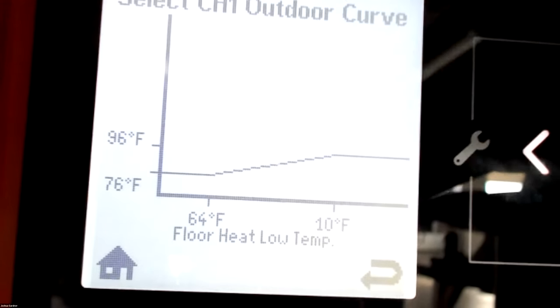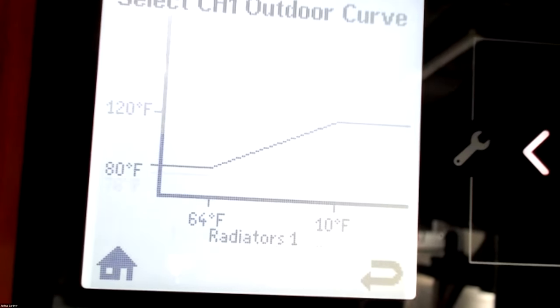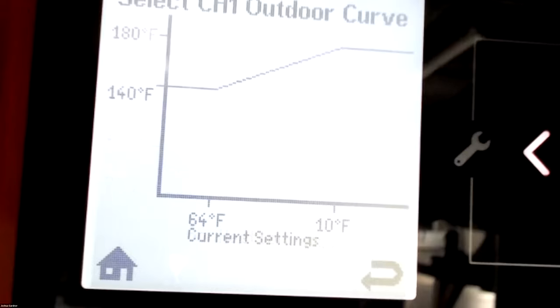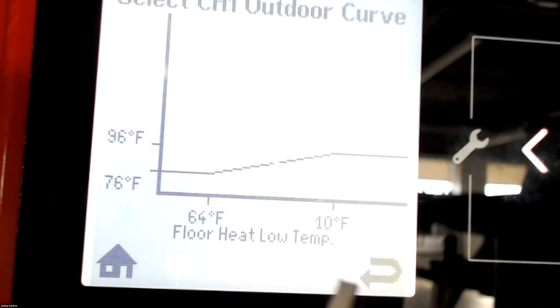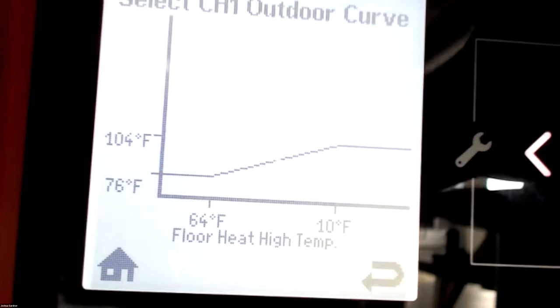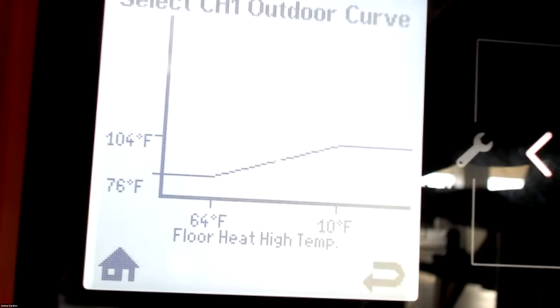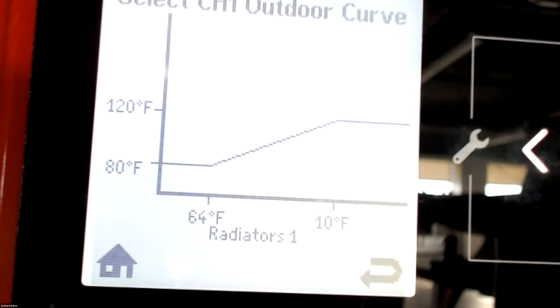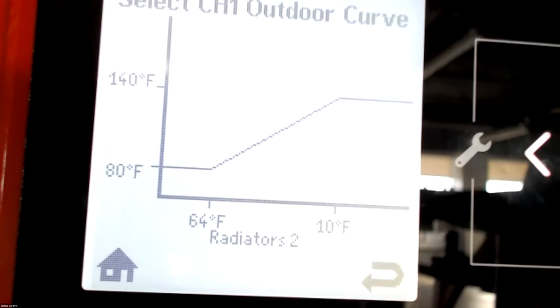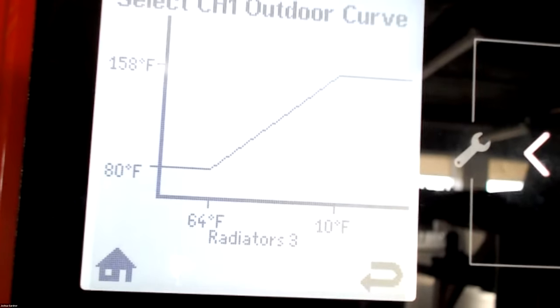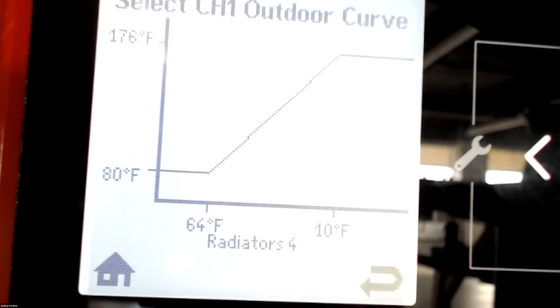So if you go and use the up and down arrows, you can see we change to some different options. It starts off with floor heating low temp, which is 10 degrees and 64 and 96 and 76, all right? So this would be like maybe in the slab or a Quik Trak on top of the floor. A little higher, 104 and 76. Radiators, so maybe a cast iron radiator, panel radiator, if it was sized, you know, designed properly, 120 on the high, 80 on the low. 10 degrees for the outdoor design. Radiators 2 goes up to 140. Radiators 3 up to 158. Radiators 4, 176 to 80.